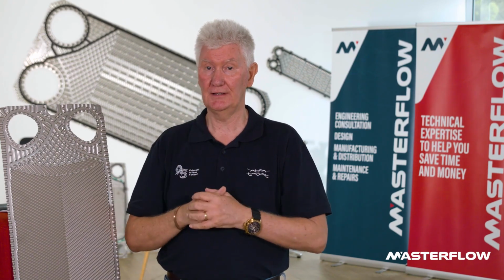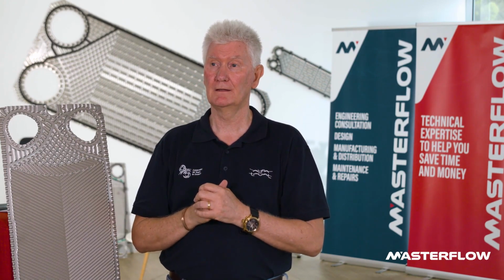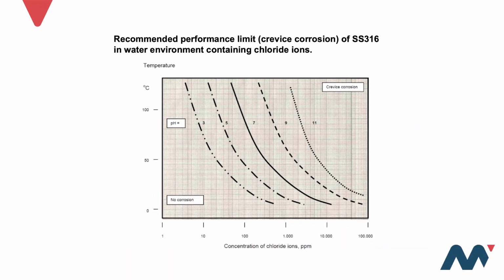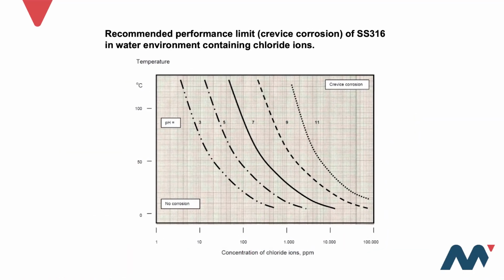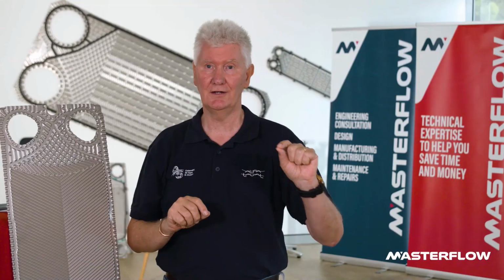If you've got, say, an ice bank, some buildings years ago were building these huge ice bank systems and then using the ice during the daytime for cooling the place. At close to sub-zero temperatures, your rate of corrosion decreases, and there's a graph where we can show you how free chlorides affect the corrosion of 304, and resistance increases as the temperature decreases, and you can get away with 304 in ice bank systems.